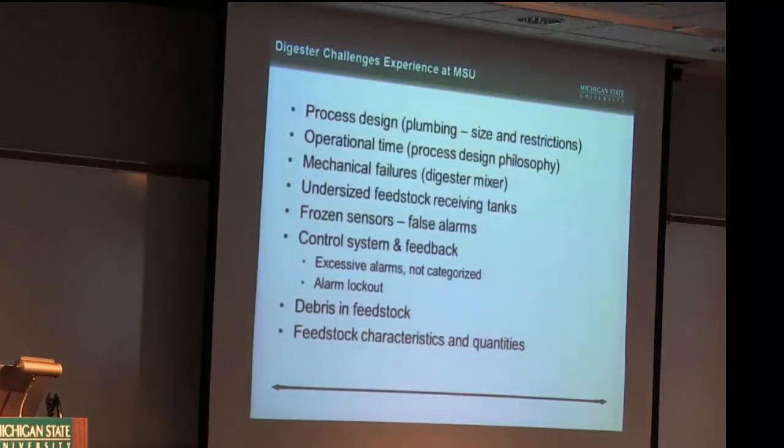We have gone through some hiccups and some challenges, probably more than we expected, but not necessarily unexpected that we'd have some. We've seen challenges really with some of the process design. We have pipe sizes that are a little bit too constricted for the type of material that we're digesting. Again, we're digesting a slurry of manure and food waste that can clog relatively easy.